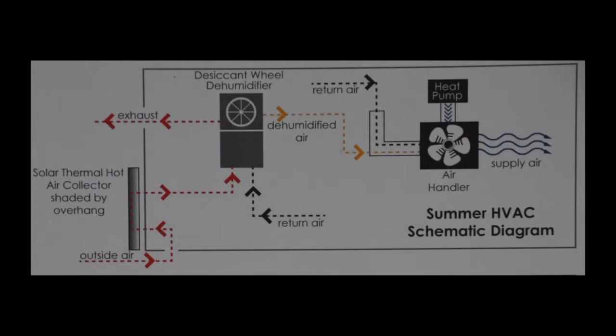In the spring and summertime, when the home needs to be cooled, the solar thermal hot air system functions in an entirely different configuration. Using a desiccant wheel dehumidifier, the solar thermal hot air system reduces the latent load of the cooling system by evaporating water vapor from the indoor environment, thereby reducing the humidity, saving energy, and increasing occupant comfort. In this configuration, return air from the house is passed over a desiccant wheel, which absorbs some of the moisture from the air. To regenerate the desiccant wheel so that it may remove more humidity from the indoor environment, the solar collector intakes outside air, which is heated from a solar thermal hot air collector, and passes it over the desiccant wheel to evaporate water from the wheel. The dehumidified return air is then sent to an air handler within the house and cooled by the house's heat pump.